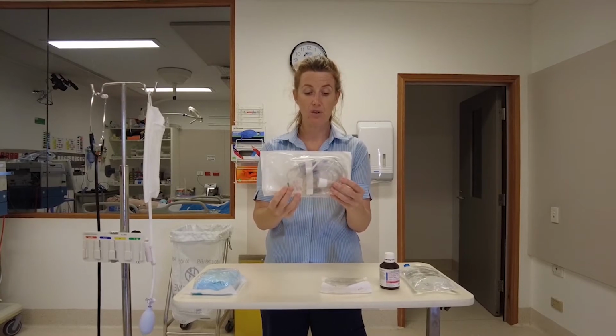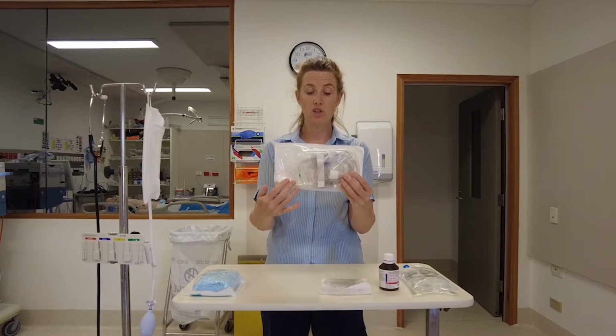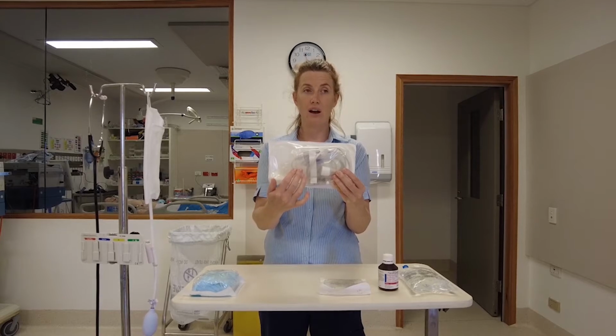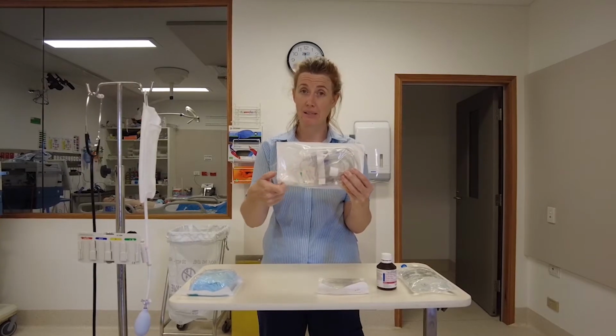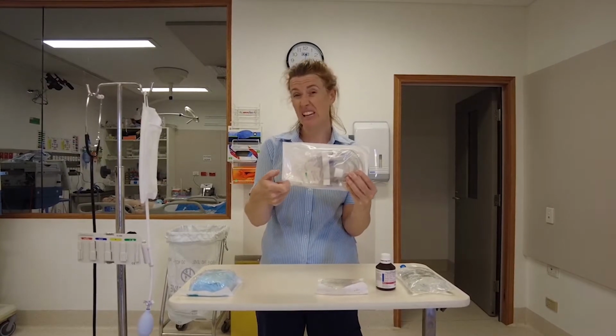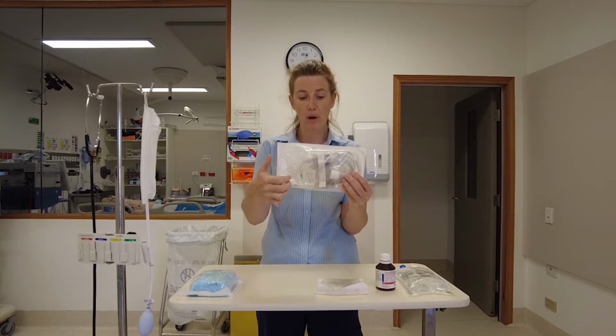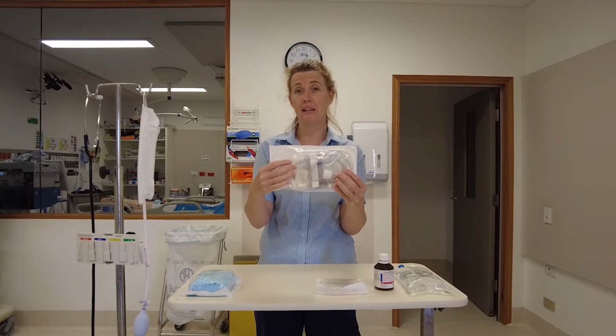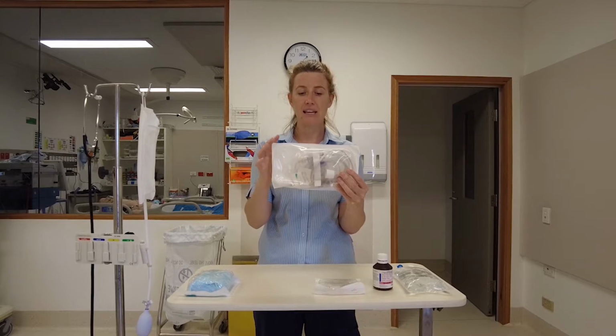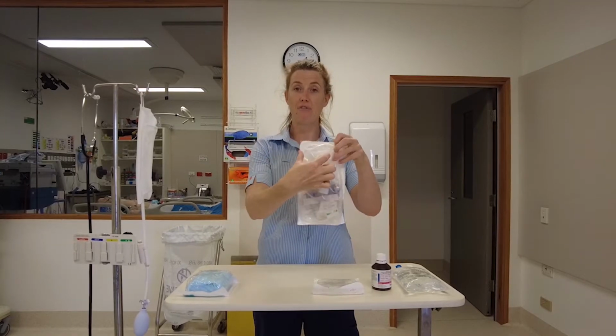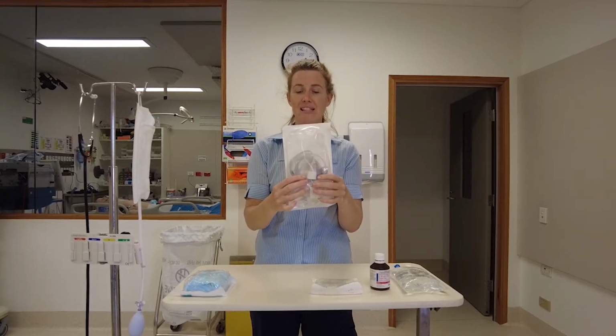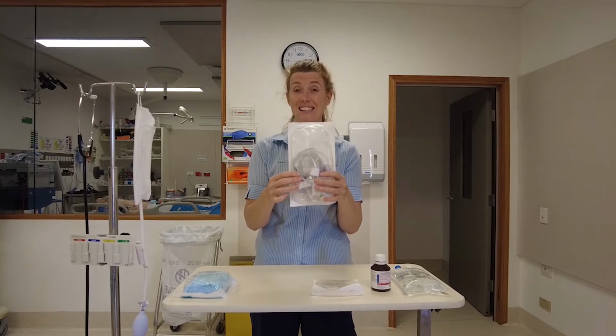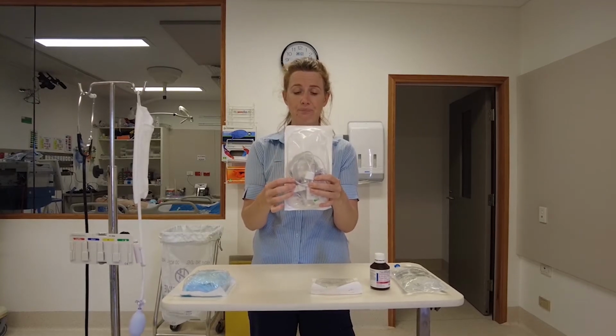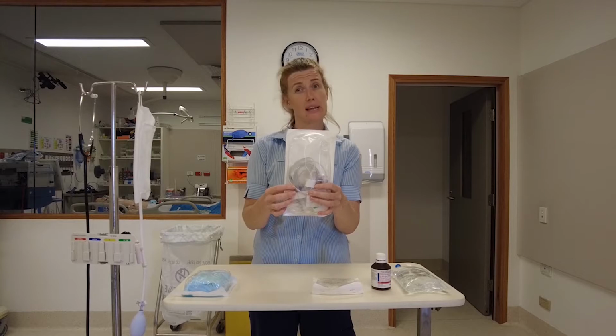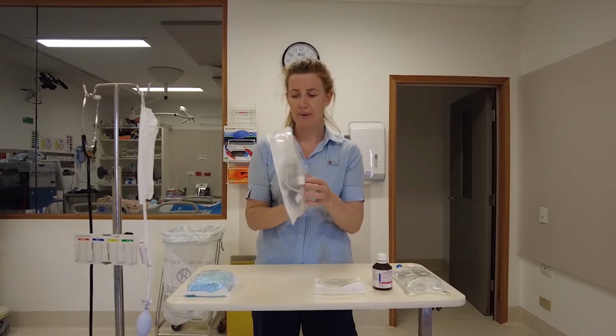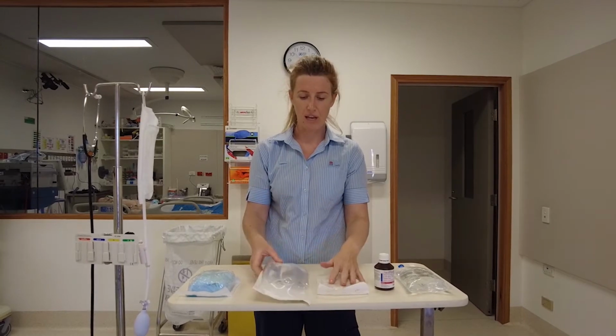Be mindful, in our unit we have two transducer kits. We have one with a vamp and the blood aspiration lever, for want of a better word, or component, and that's the one we typically use in arterial lines. There is a kit that comes in a package that's about half the size of this, and that doesn't have that blood aspiration component. It is literally just the transducer setup, and we would use that for things like a CVP. So important to make sure that you get the right kit.